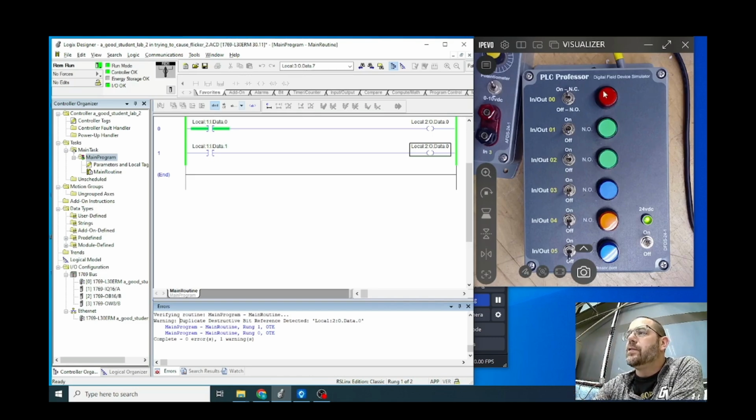So this flickering should be a little bit concerning to us. Part of what I want you to hear is that when I'm executing a ladder logic program on my PLC, it's constantly going through all of the rungs pretty quickly, sometimes 2 to 4 milliseconds, sometimes maybe 40 or 100 milliseconds, but it's doing a lot. It's just constantly looping through, and so I don't always know where in the code I am. It's possible that sometimes it'll hang up on one rung or another. We're seeing this flickering because occasionally this one wins, but most of the time this one is winning.